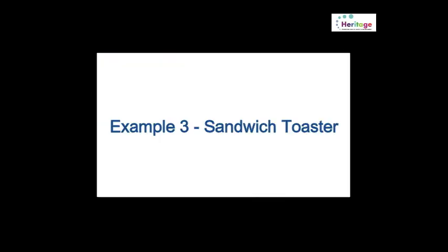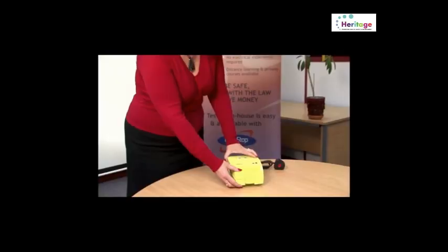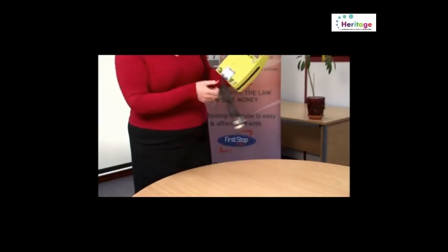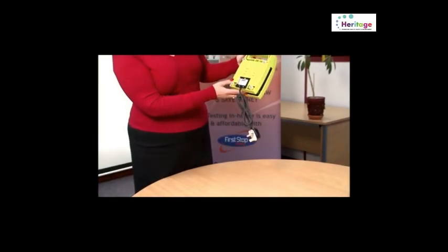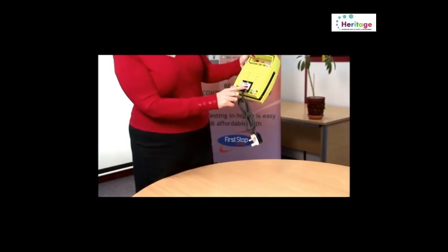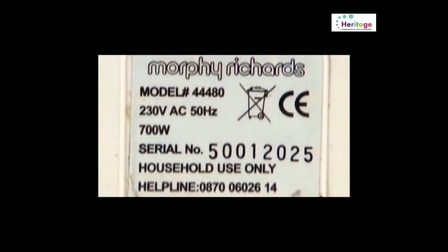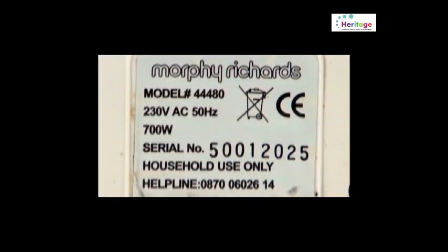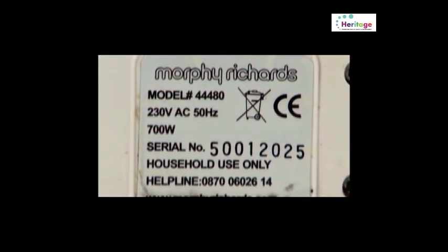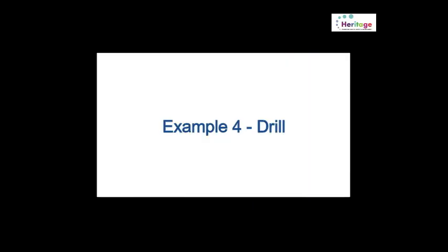Example 3. Sandwich toaster. This sandwich toaster has a plug fitted with a 13 amp fuse and, according to its rating plate, has a power consumption of 700 watts. As this is right on the decision threshold, what should we do? In general, heating appliances are fitted with a 13 amp fuse and this can be left in place.